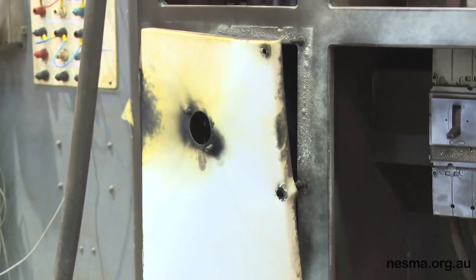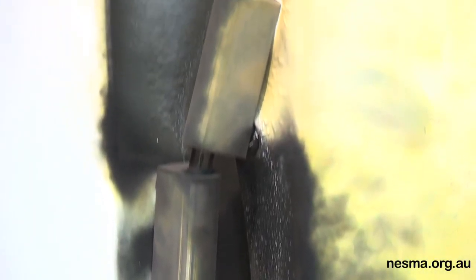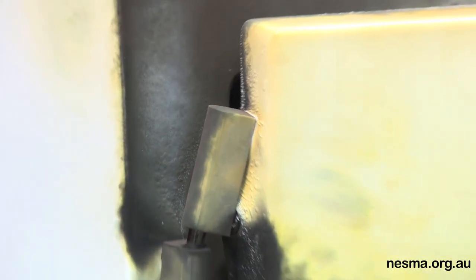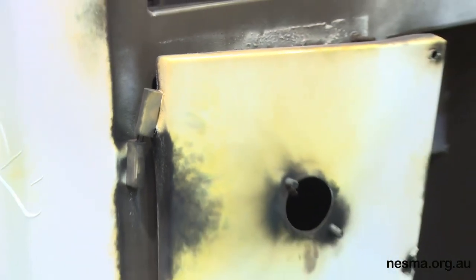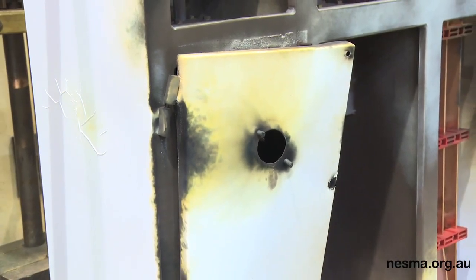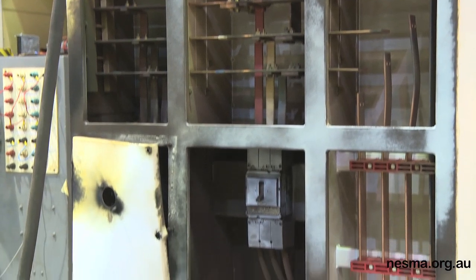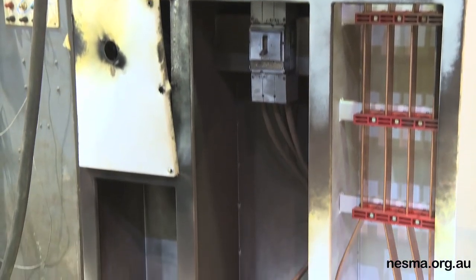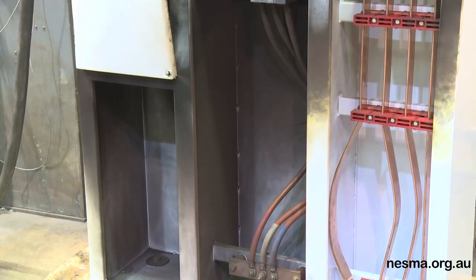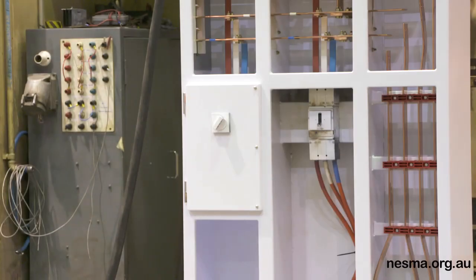That said, a fault can occur if the board were under some sort of repair, the circuit breaker was off and someone had left their screwdriver, or had not terminated the circuit breaker correctly, or there was some contamination on the line side.